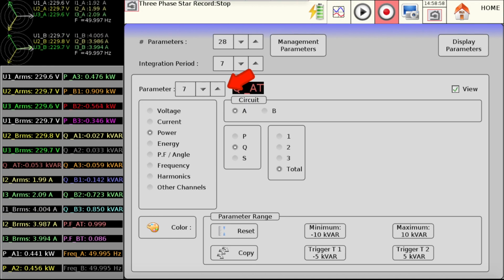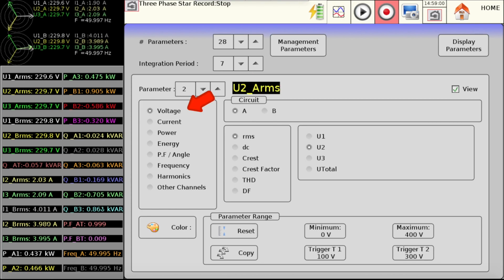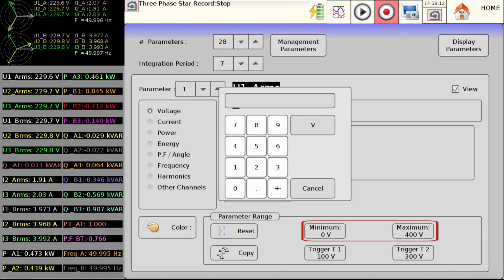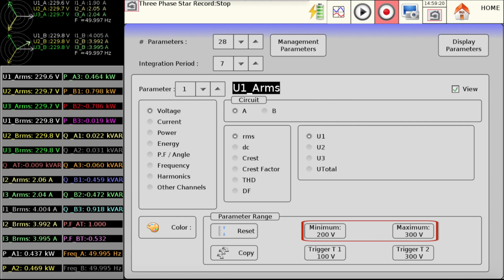Let's select our parameter number 1, which is the voltage in RMS on our circuit A with U1. We know that our voltage is about 230 volts. So, we set a minimum display at 200 volts and a maximum display at 300 volts to limit the scale on our recording.